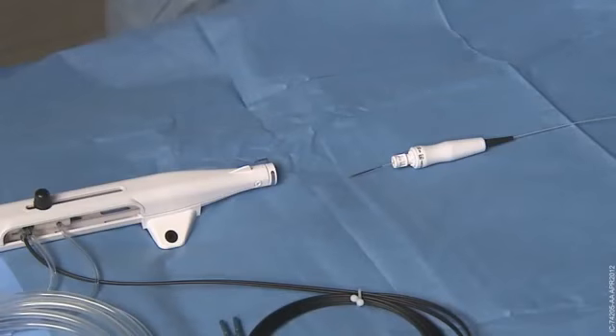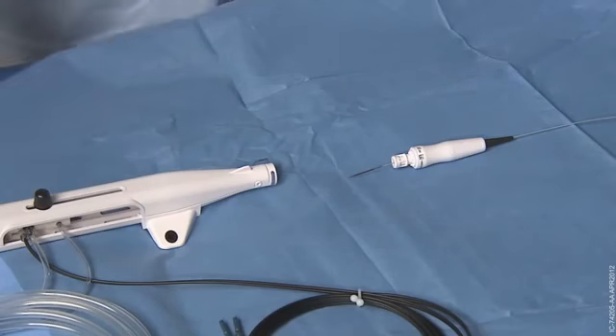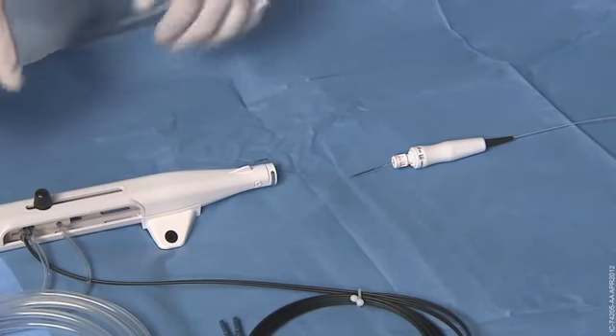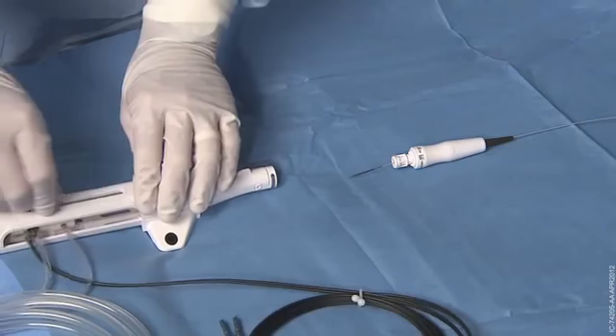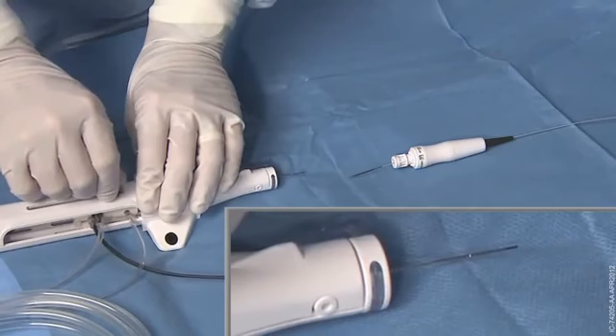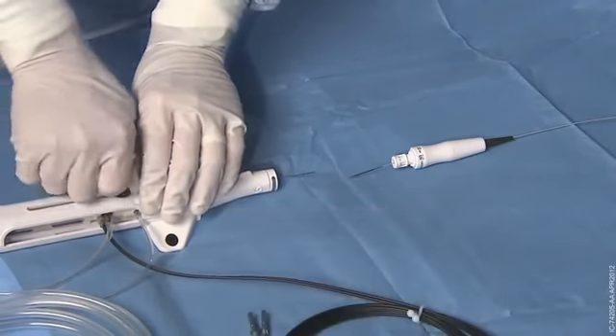The catheter advancer connection has 2 major steps. First, make the drive shaft connection. Loosen the advancer knob and slide forward to expose the drive shaft connection. With the drive shaft exposed, tighten the knob to lock it in position.